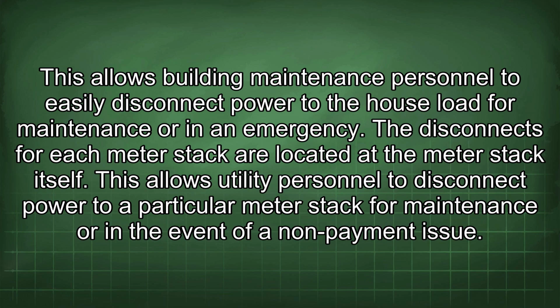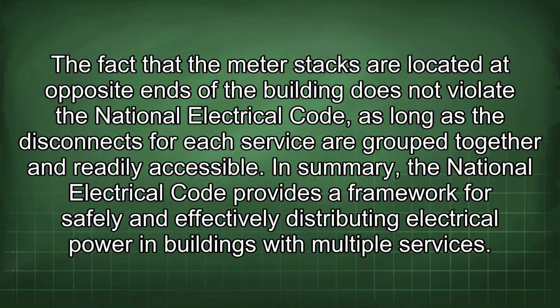The disconnects for each meter stack are located at the meter stack itself. This allows utility personnel to disconnect power to a particular meter stack for maintenance or in the event of a non-payment issue. The fact that the meter stacks are located at opposite ends of the building does not violate the National Electrical Code, as long as the disconnects for each service are grouped together and readily accessible.